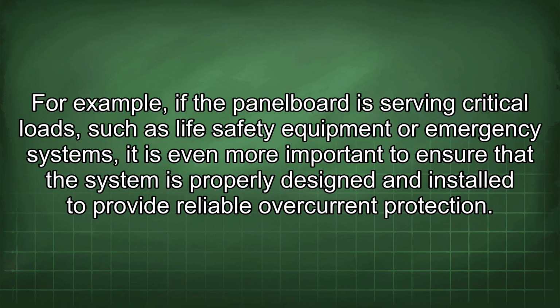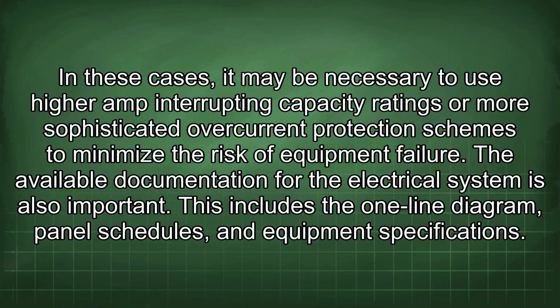For example, if the panelboard is serving critical loads such as life safety equipment or emergency systems, it is even more important to ensure that the system is properly designed and installed to provide reliable overcurrent protection. In these cases, it may be necessary to use higher amp interrupting capacity ratings or more sophisticated overcurrent protection schemes to minimize the risk of equipment failure.